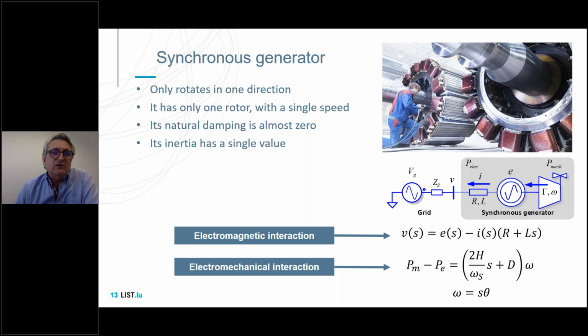The inertia has a given value, and we claim inertia, but inertia is not always good. When you need to stop the system, inertia is against you. When there is a fault and it's necessary to disconnect or speed up a generator quickly, the inertia would not allow the regular governor to do that, and this is why it is necessary to use PSS, which directly regulate the exciters of the synchronous generator. So the electromechanical response of the synchronous generator itself is quite slow.